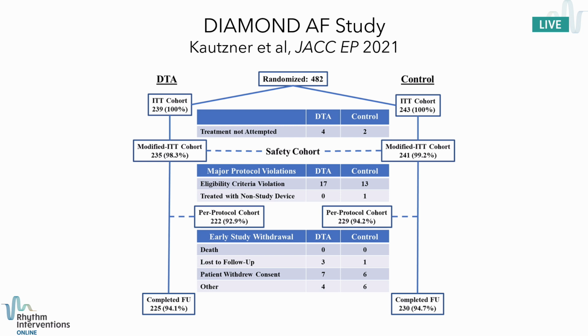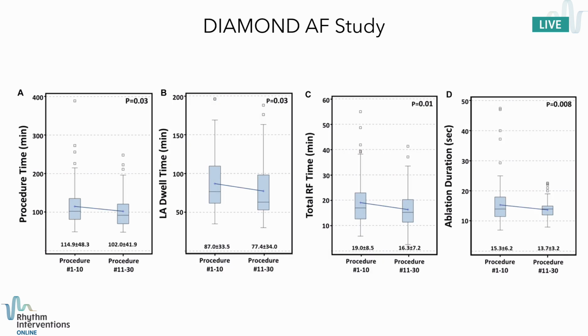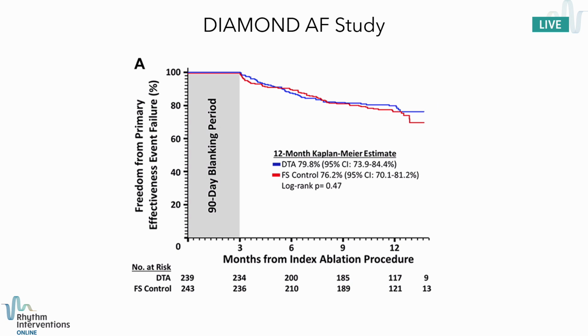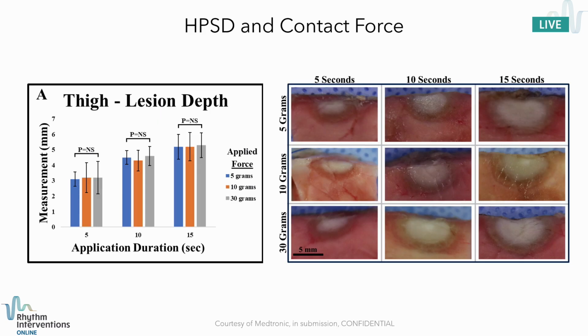From the diamond tip perspective, there was a randomized study using the diamond tip catheter system versus a control sort of TactiCath type ablation system. And these patients were all followed up for a year. What was very interesting is that by using power modulated, temperature controlled ablation, there was actually a reduction in procedure time, whether it was total ablation duration, RF time, or LA dwell time, compared to a purely contact force guided mechanism. And furthermore, the absence of contact force did not seem to alter the results in any way, because operators were able to target a tissue temperature, which became a very powerful surrogate for contact force. Or maybe I should say it the other way, contact force is but a surrogate for tissue temperature.